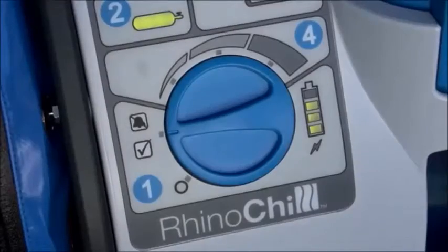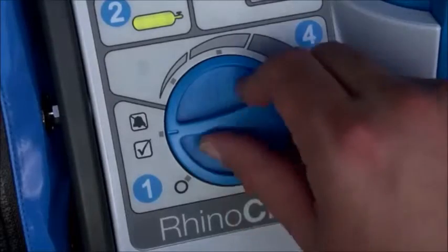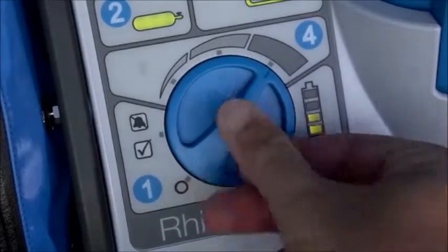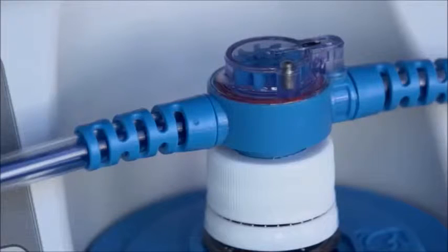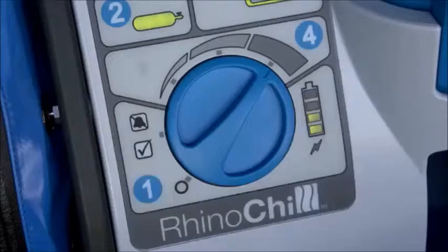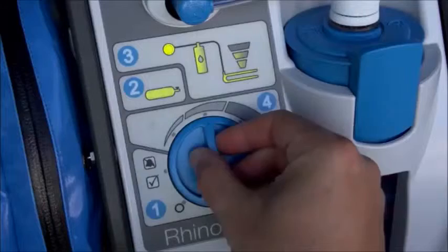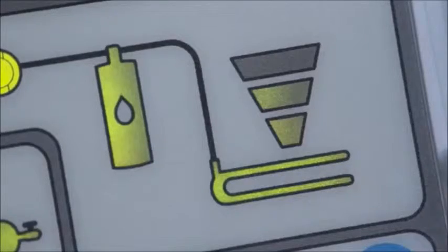The device is now ready to deliver the cooling vapor and start the induction of hypothermia. Turn the flow rate to high for 30 seconds or until the liquid flow indicator rotates briskly. Once the indicator is rotating, turn the setting control knob to the desired flow rate and the green flow indicator will illuminate. Medium and high flow rates are to be used for initiating cooling, with the low flow rate reserved for maintenance cooling. If using the device to treat a neurological patient with increased intracranial pressure or pyrexia, the high flow rate should be selected as their initial treatment rate.